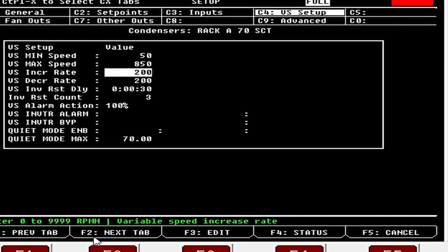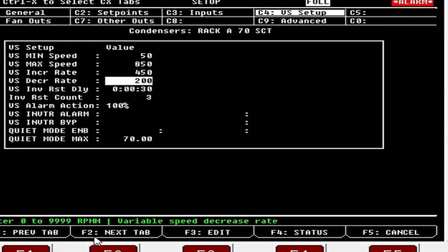This is how fast the controller ramps the motors up and down. I see guys putting these at 2000 — that is the absolute worst thing you could do, it just makes the system hunt all over the place. I generally go 350 on the increase rate and 450 to 500 on the decrease rate — I make the decrease rate faster. You want it slower to ramp up so you don't overshoot, and faster to decrease so you don't undershoot. Inverter Reset Delay is how long it takes to reset the inverter after a fault, and Inverter Reset Count is how many times it'll try to reset.